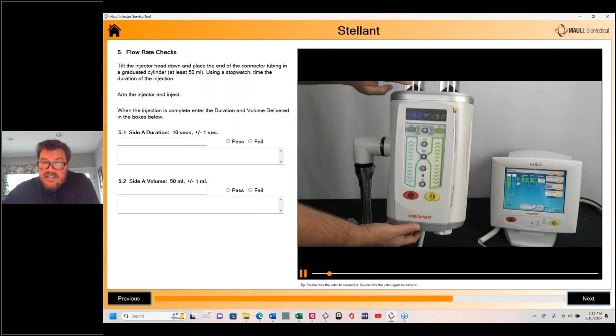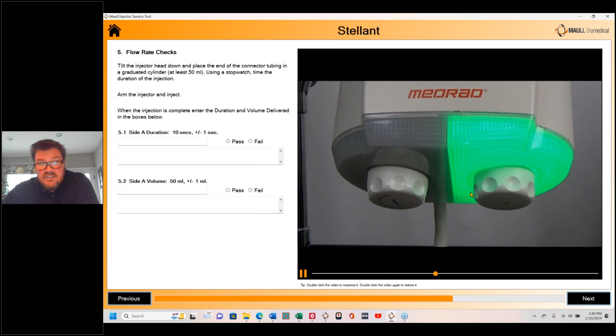So we're going to get a graduated cylinder. We're going to tilt the injector head down. We're going to arm the injector. Get our graduated cylinder. Get our stopwatch. Did I do the stopwatch? Yep, there's the stopwatch. Arm the injector, and as soon as the injector is armed, those flashing lights there mean the system is armed. So for side A, we obviously do this one at a time. For the A side syringe, which is contrast, we expect a duration of 10 seconds and a volume of 50 milliliters, plus or minus 1 second, plus or minus 1 milliliter.